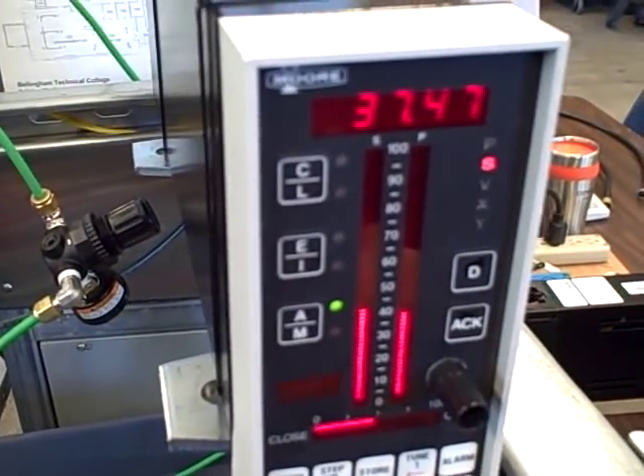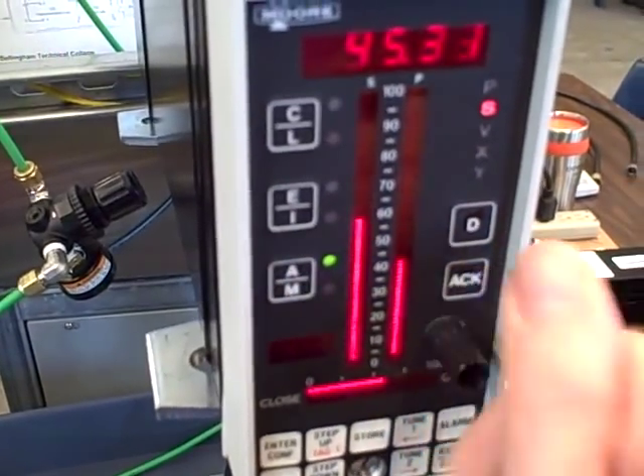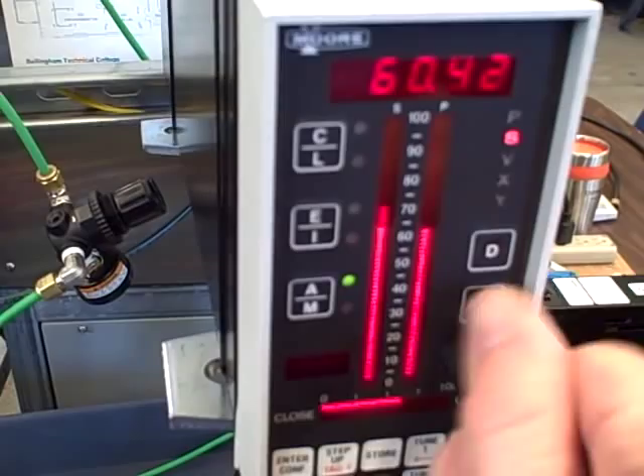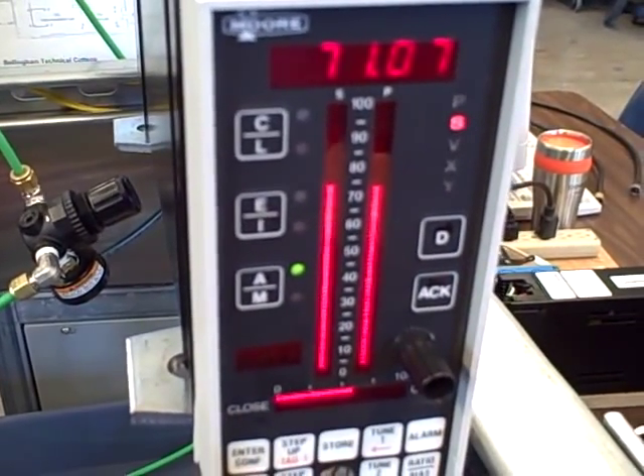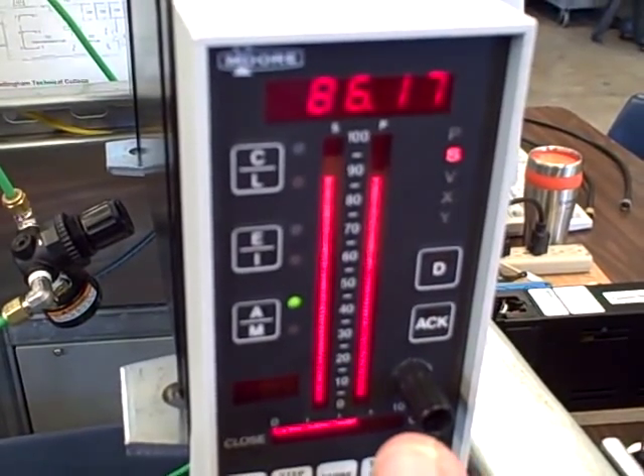So a little bit of error there. Probably need a little bit more integral action. There we go. Came up to the set point pretty quickly. No overshoot, no oscillation.